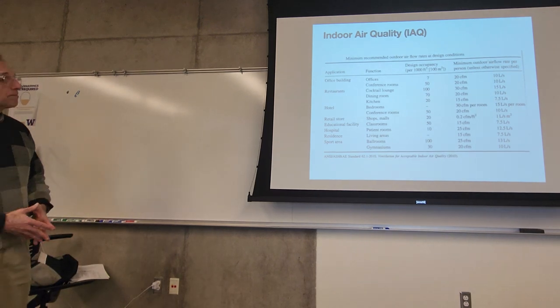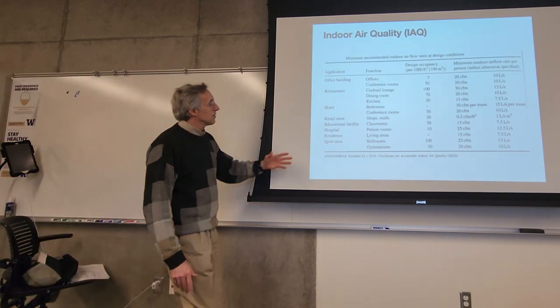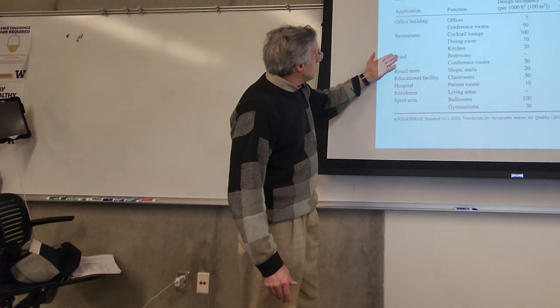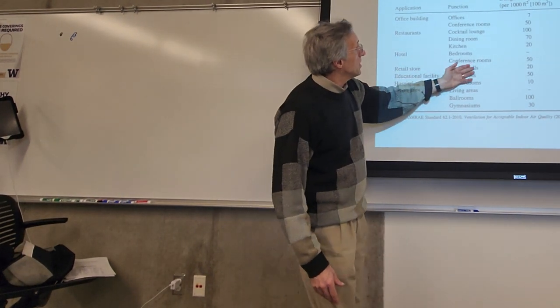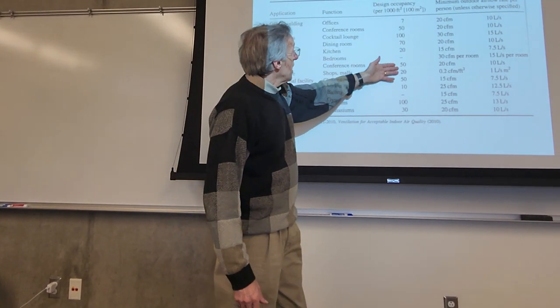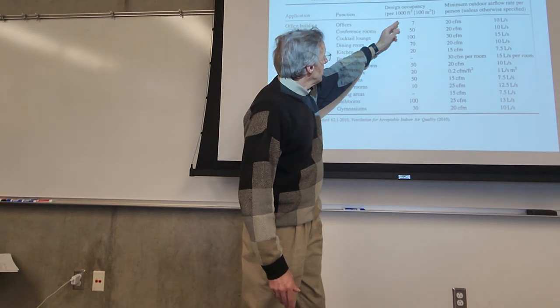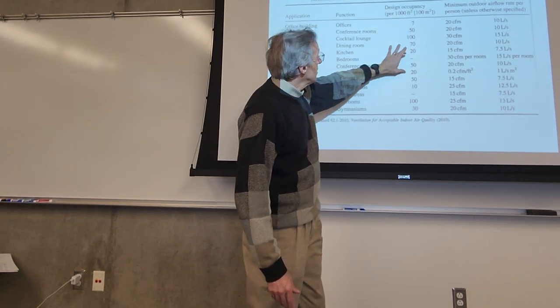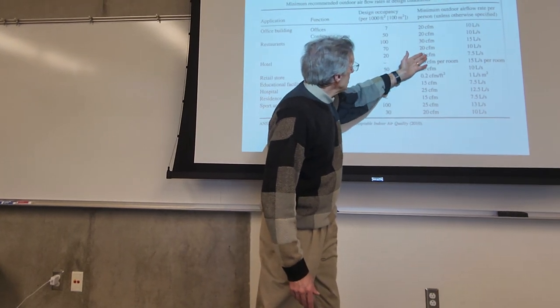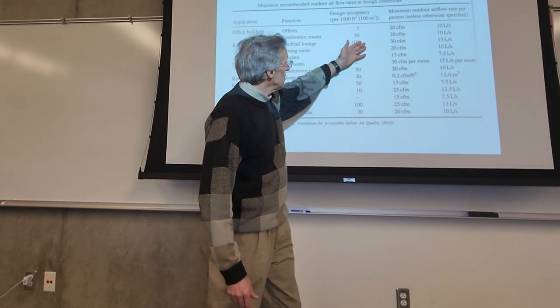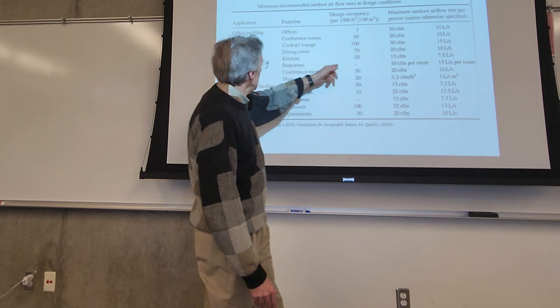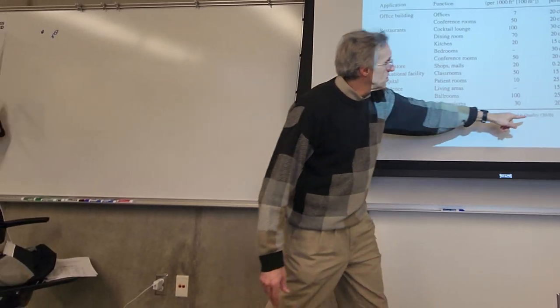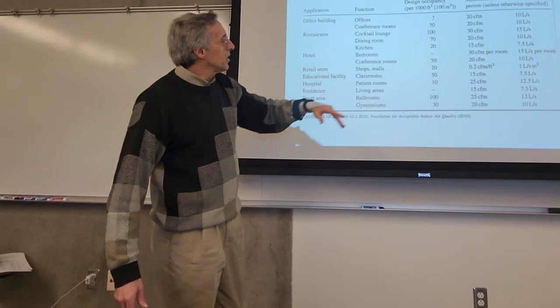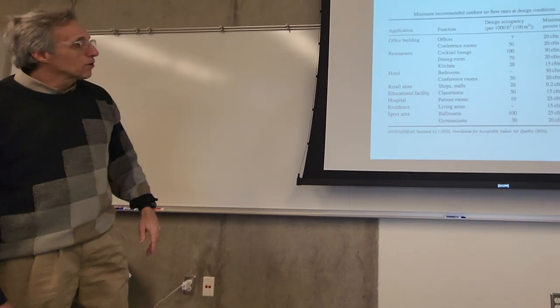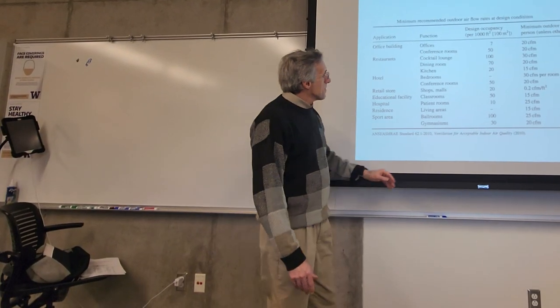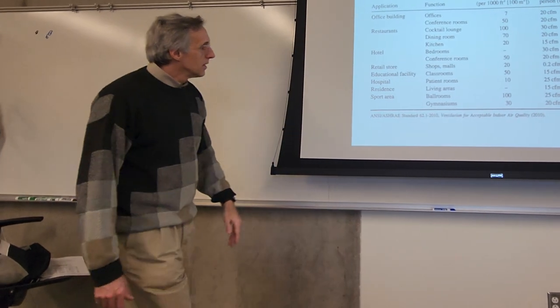Actually, this is kind of a segue into the next stuff. Looking at the different types of buildings, their function, and then there's a design occupancy. This is the maximum number of people per 1,000 square feet, and then how much ventilation you're supposed to have per person. See, 20 is kind of a minimum. It's 15, maybe older. Yeah, 2010. This is not current here. I think the one in our book would be current. But for different areas.